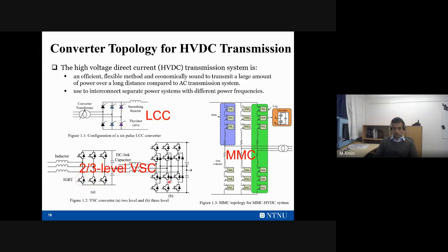And recently, another converter has appeared, called the modular multi-level converter. This brings many more advantages. It reduces the filter requirement a lot, since with multiple levels we can generate the sinusoidal voltage with many levels, which reduces the requirement of the filter. So those are the main converter topologies now used in modern high voltage direct current transmission systems. And this modular multi-level converter is gaining popularity, and now most systems are using the modular multi-level converter in high voltage direct current transmission.